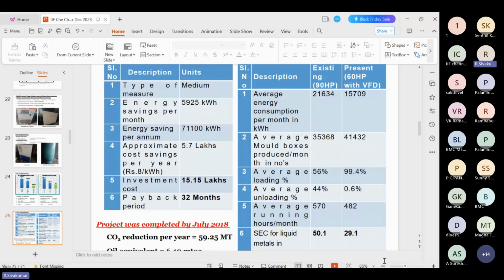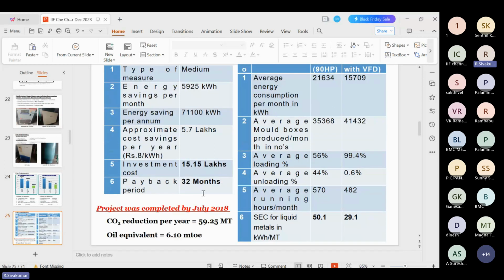The overall investment cost is 15.15 lakhs. The energy saving per annum is 71,100 units. The approximate cost saving at the rate of 8 rupees is 5.7 lakh rupees. So the payback period will be 32 months. Due to this adaptation, the unit saved 71,100 units of electricity. That is equivalent to 6.10 tonnes of oil equivalent. As I already said, 71100 into 860 divided by 10 power 7 gives 6.1 tonnes of oil equivalent. And CO2 reduction is also 59.25 metric tons.